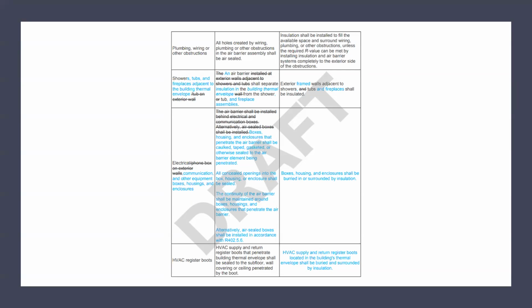Electrical, communication, and other equipment boxes, housing, and enclosures have been changed to encompass all equipment and enclosures and removes the on exterior wall designation. So where this comes into play, a lot of times where I saw them installed were on the garage wall. And if it was on the garage wall, a lot of people said, well, that's not an exterior wall, so I don't have to follow that requirement.